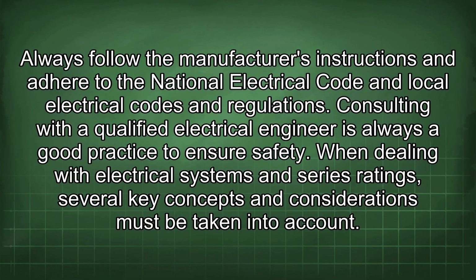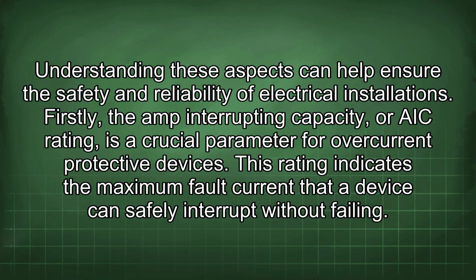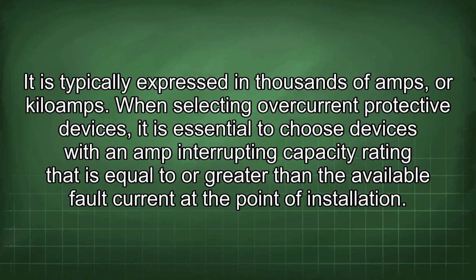When dealing with electrical systems and series ratings, several key concepts and considerations must be taken into account. Understanding these aspects can help ensure the safety and reliability of electrical installations. Firstly, the amp interrupting capacity, or AIC rating, is a crucial parameter for overcurrent protective devices. This rating indicates the maximum fault current that a device can safely interrupt without failing. It is typically expressed in thousands of amps, or kiloamps. When selecting overcurrent protective devices, it is essential to choose devices with an amp interrupting capacity rating that is equal to or greater than the available fault current at the point of installation.